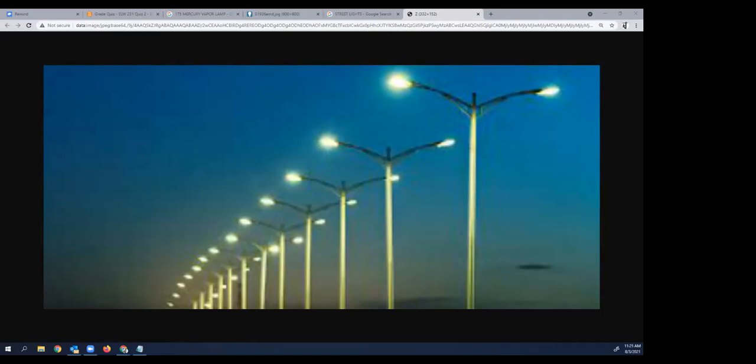Safety built in as far as the engineer side of it too. Showing this pole up here, it's you as the installer that needs to know what to do. How many runs of number 12 do I need in one individual pole, 1 or 2? 2, because there's 2 heads. Somebody brand new might think, well, I'm just going to go 1 run here and then go across the arms. Nope, that's not allowed. So that's in a work practice, not in an engineering type thing. Those are things that you just kind of learn at work.